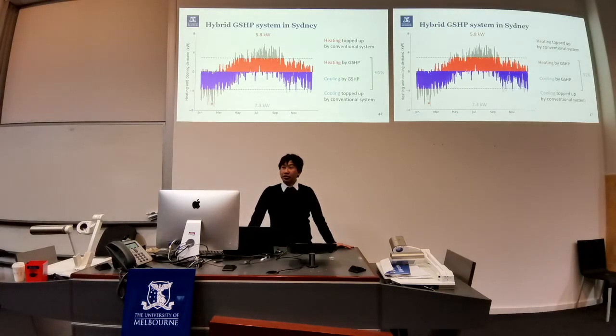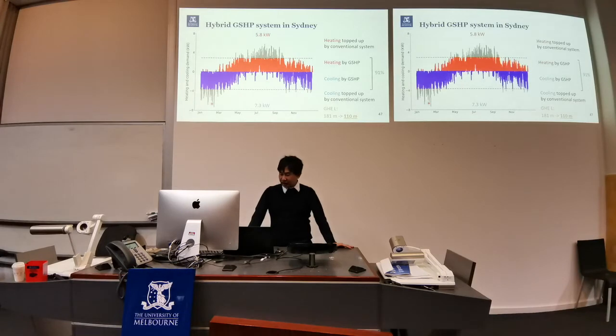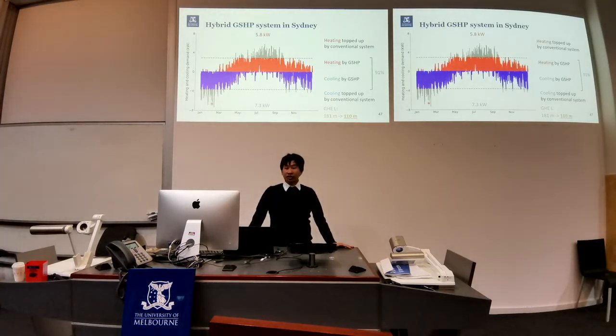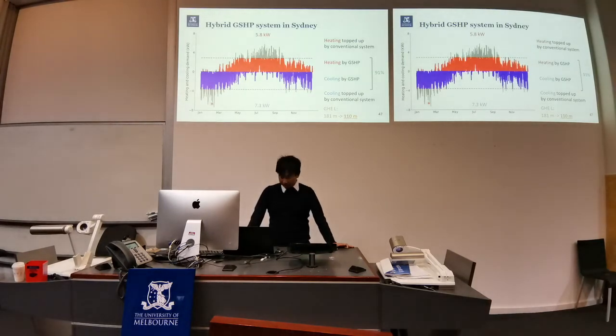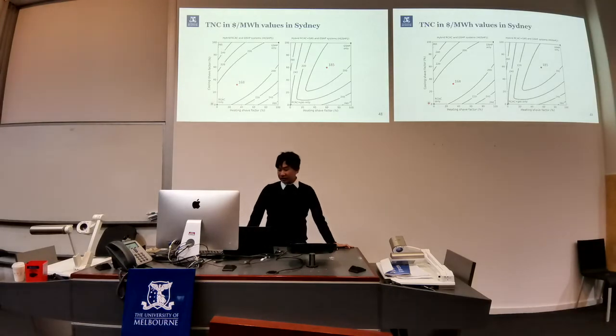Doing it this way will reduce the peak capacity of the heat pump effectively by half, which in turn will reduce the ground heat exchanger length as well as the capital cost required to install the system. But how do we know what is the best shape factor to install this hybrid system at? Here, I present the results from two hybrid systems in Sydney.